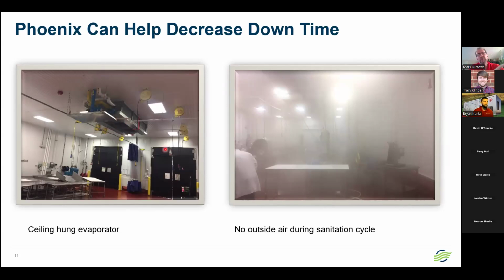Before you switch, Brian, so everyone's clear on this. The photograph on the left is probably pre-op, probably 5 o'clock in the morning. There's nothing wrong with the ceiling hung evaporators. A lot of plants use them. There is no fresh air in this room whatsoever. When they go into sanitation mode and they take the hot water hose, 140, 150 degrees off that boiler, and that room's been 42 degrees, again, you get this instant vapor that travels up.